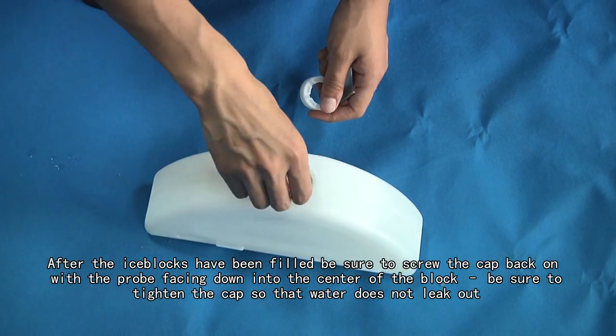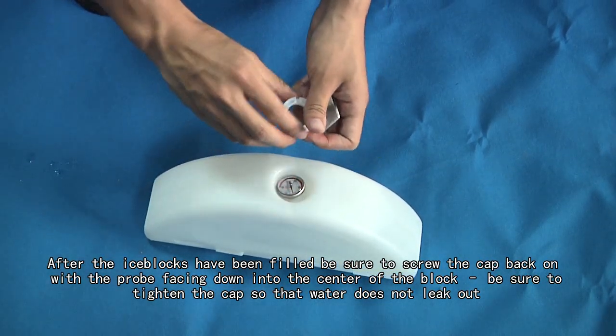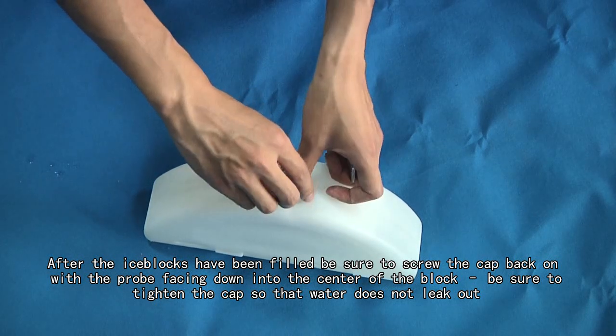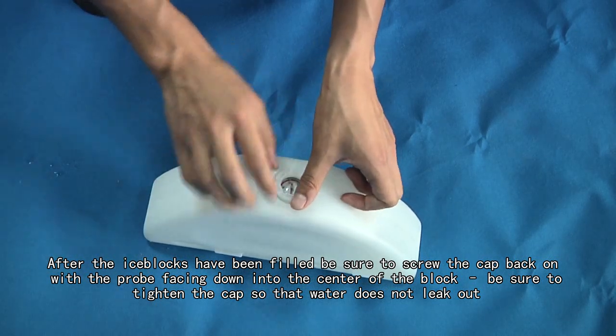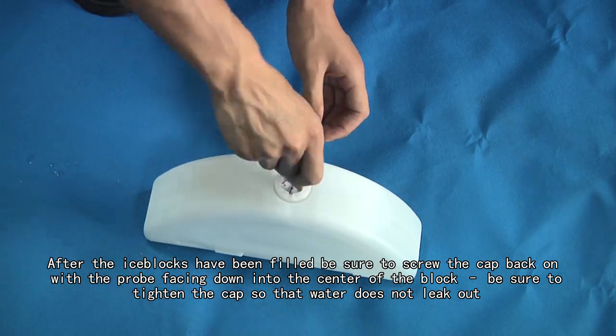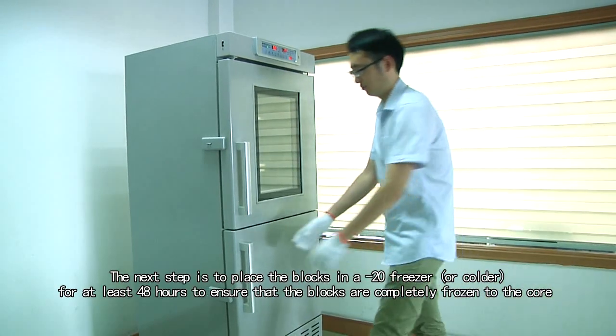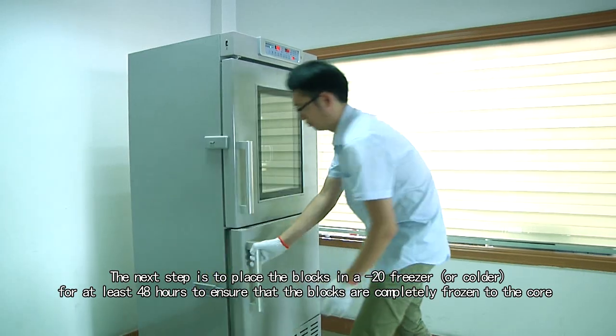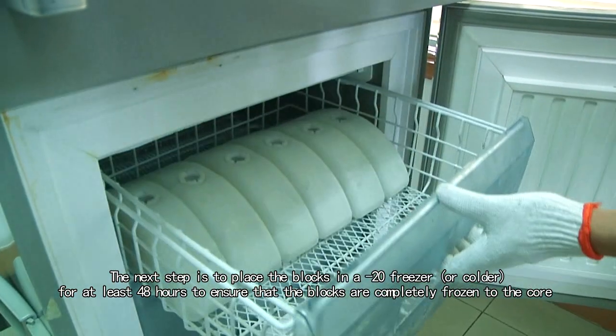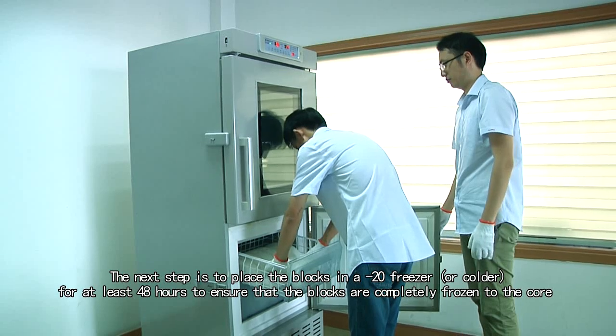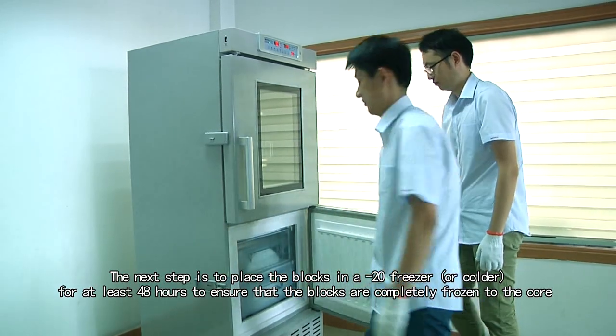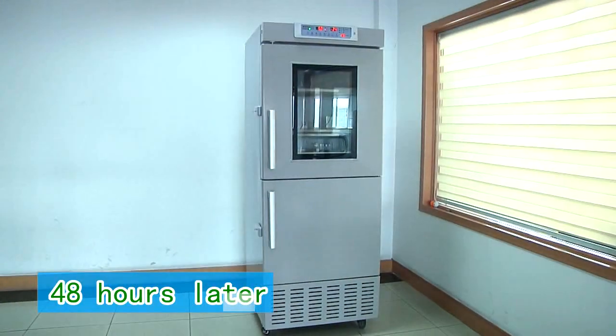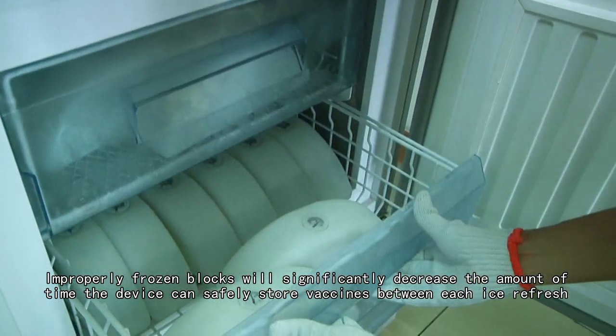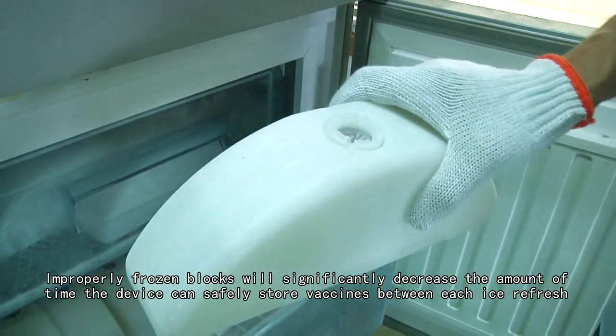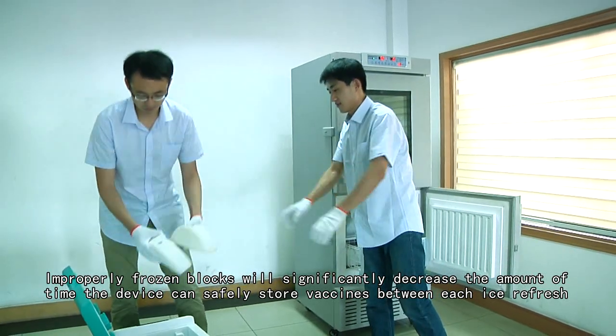After the ice blocks have been filled, be sure to screw the cap back on with the probe facing down into the center of the block. And be sure to tighten the cap so that water does not leak out. The next step is to place the blocks in a -20 freezer for at least 48 hours to ensure that the blocks are completely frozen to the core. Improperly frozen blocks will significantly decrease the amount of time the device can safely store vaccines between each ice refresh.